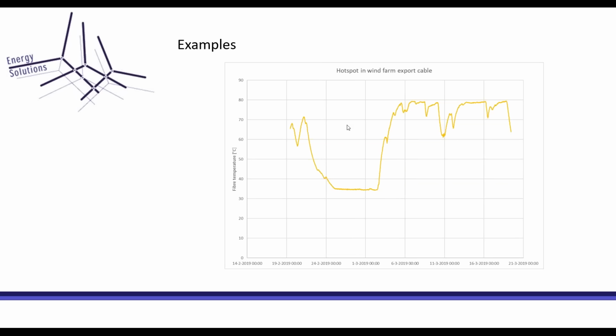There was a period of time where there was not a lot of wind, so the cable cooled down. But then for a long number of days, there was a high wind on the wind farm. And at one moment they had to limit it to, in this case, 80 degrees fiber temperature, which then is the 90 degrees conductor temperature. But we can be pretty sure that if they wouldn't have limited the cable, they're far off the design limit of the cable. So they both probably would have failed in that case, and it would have cost a lot of money to do the repairs, and also the missed revenue on the production.